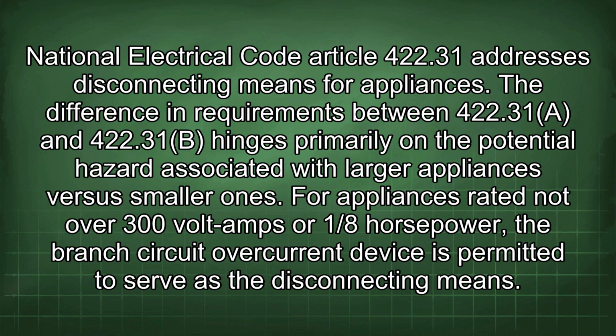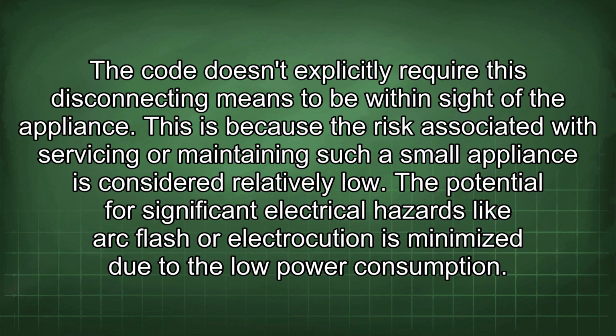For appliances rated not over 300 volt-amps or 1/8 horsepower, the branch circuit overcurrent device is permitted to serve as the disconnecting means. The code doesn't explicitly require this disconnecting means to be within sight of the appliance. This is because the risk associated with servicing or maintaining such a small appliance is considered relatively low. The potential for significant electrical hazards like arc flash or electrocution is minimized due to the low power consumption.